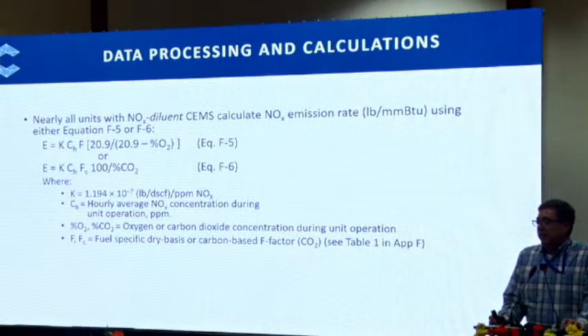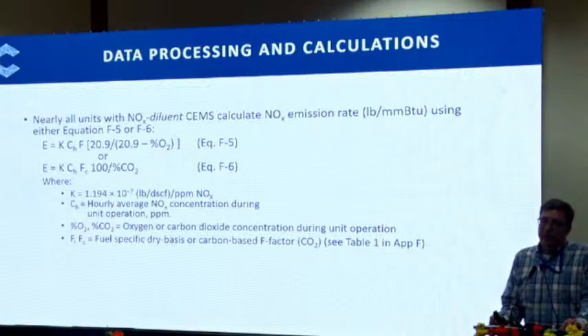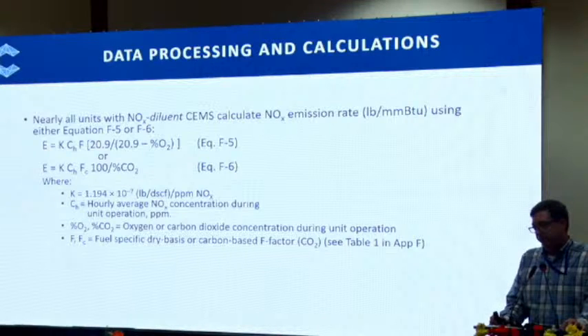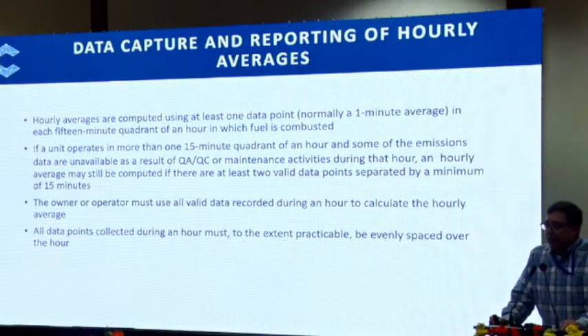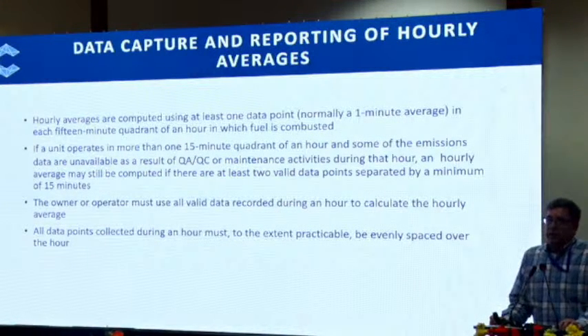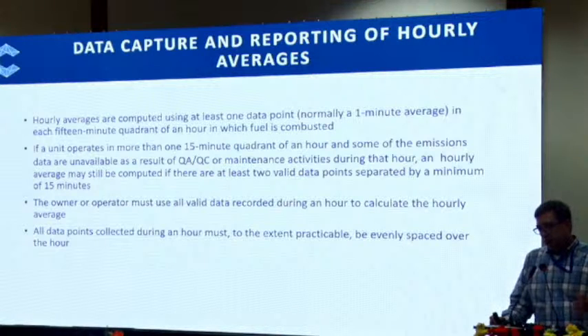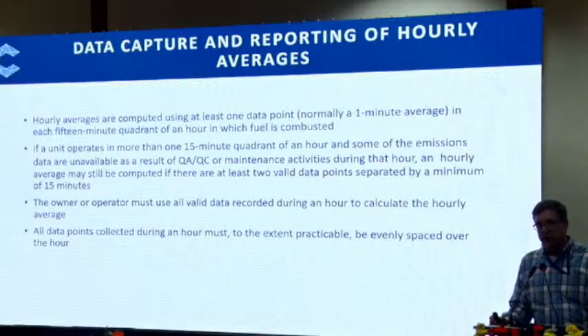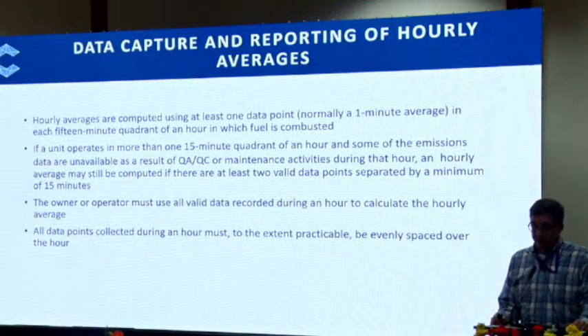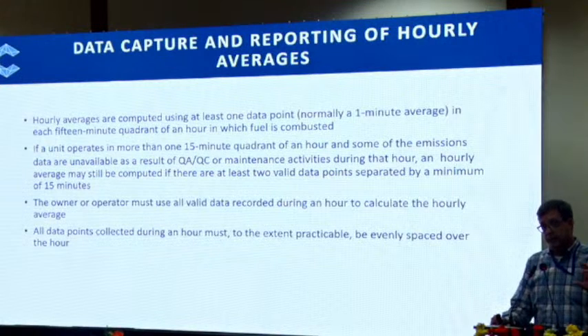Nearly all units with NOx diluent CEMS calculate NOx emissions rates using either of these two equations. So one is O2 based and one is CO2 based. Again, that can be wet or dry depending on the type of system you have. Data capture and reporting of hourly averages. Historically, we collect data on a frequency of 1 minute averages. Those 1 minute averages are kept for approximately 3 hours, and then they are generated into 1 hour averages. And those 1 hour averages are used to report accordingly to the permit and the regulatory guidelines. That can be a 1 hour average, a 3 hour average, or a 4 hour average. It really depends on the regulation.